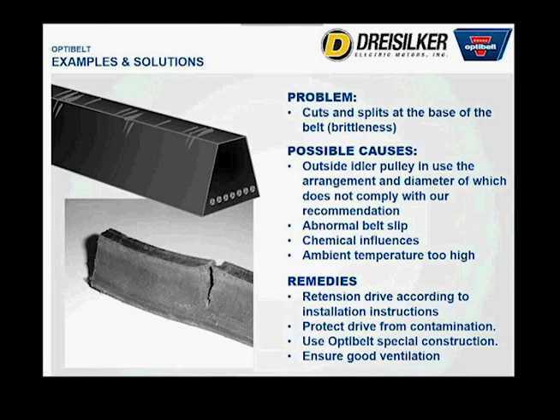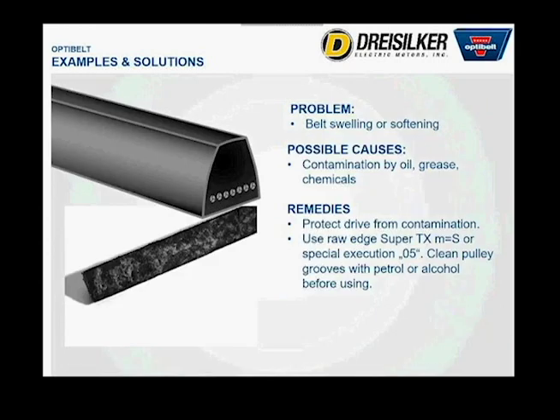Or any sort of abnormal belt slip. So if your tension is too low, the belt starts slipping, it builds up heat, and this vulcanizes the rubber even further, and then it starts cracking, becomes brittle and hard, and then can't do its job. Or any sort of chemical influences. And then temperature too high. So again, remedies are to retension your drive, protect it from contamination, and make sure the temperature in there is not getting too high. It's mostly applicable near gas engines or any sort of exhaust or ventilator fans over kitchens.